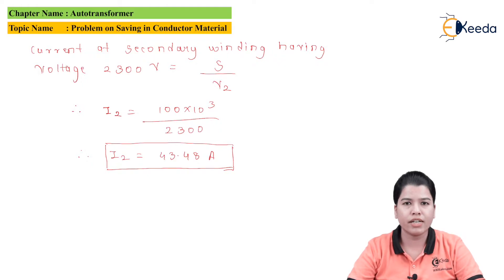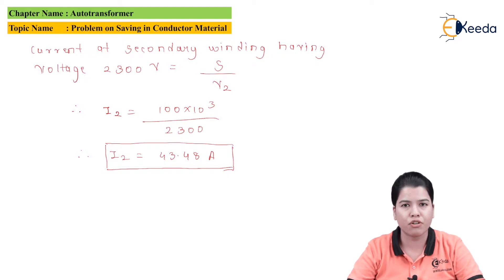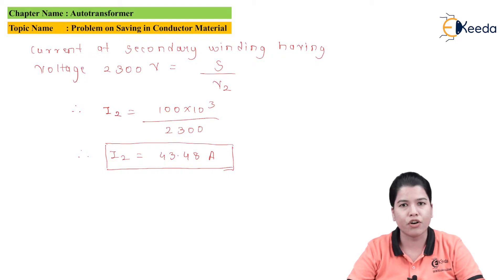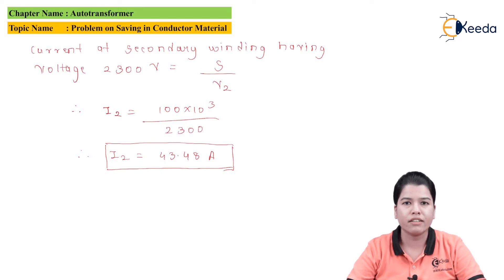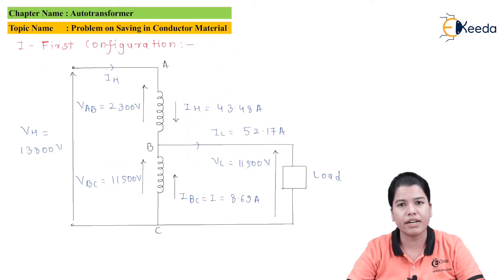These are the two currents when the transformer is considered as a two winding transformer. If we want to use the same transformer as an auto transformer, the two windings have to be connected in series. When this transformer operates as the auto transformer, the currents in the primary and secondary windings will not exceed their rated values, so these will be the currents for the auto transformer as well. We have to consider two configurations in which the auto transformer windings can be connected.